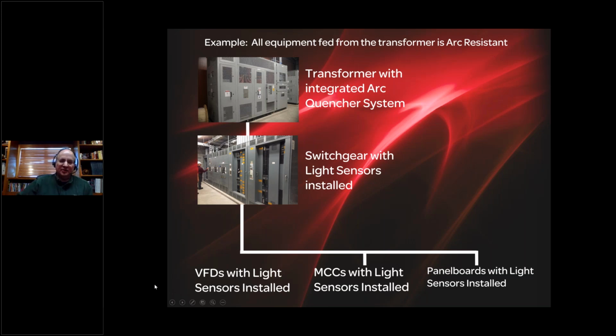becomes arc resistant. And that switchboard in this example is feeding variable frequency drives, motor control centers, and panel boards, all with light sensors installed. Everything you see here from the switchboards, including the VFDs, MCCs, and panel boards, all then becomes arc resistant.